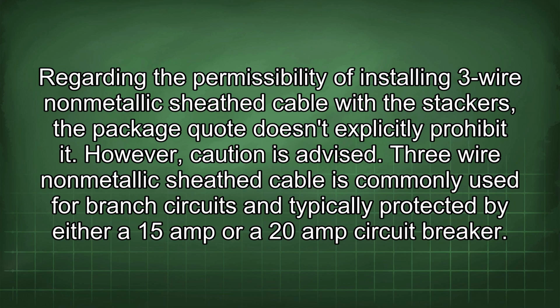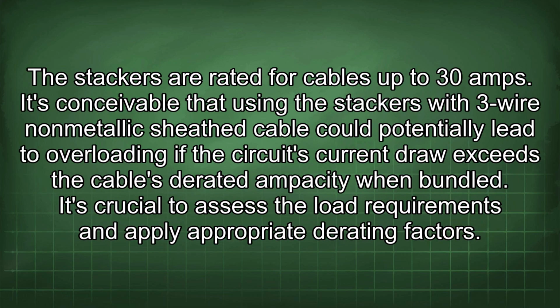However, caution is advised. 3-wire non-metallic sheath cable is commonly used for branch circuits and typically protected by either a 15-amp or a 20-amp circuit breaker. The stackers are rated for cables up to 30 amps. It's conceivable that using the stackers with 3-wire non-metallic sheath cable could potentially lead to overloading if the circuit's current draw exceeds the cable's derated ampacity when bundled. It's crucial to assess the load requirements and apply appropriate derating factors.